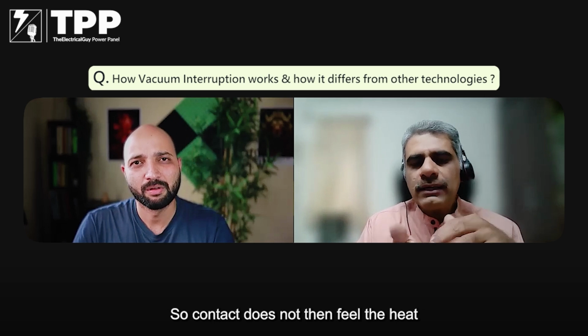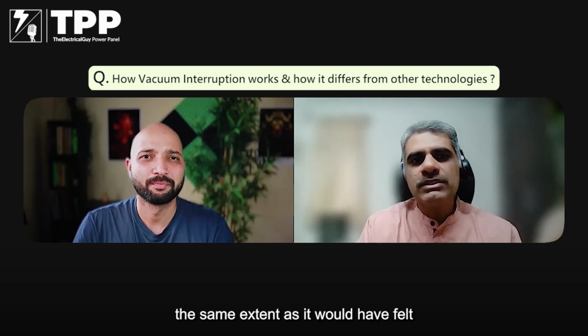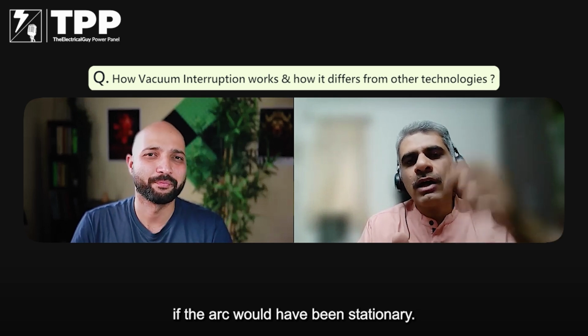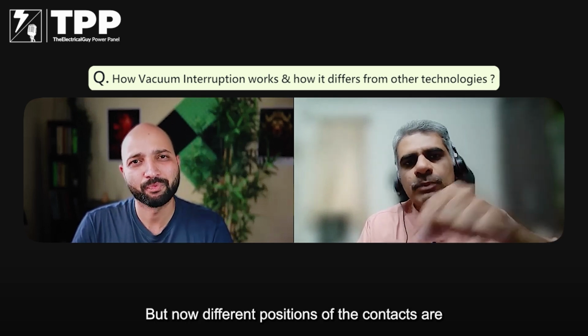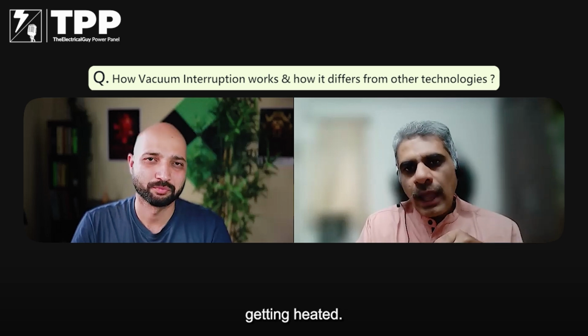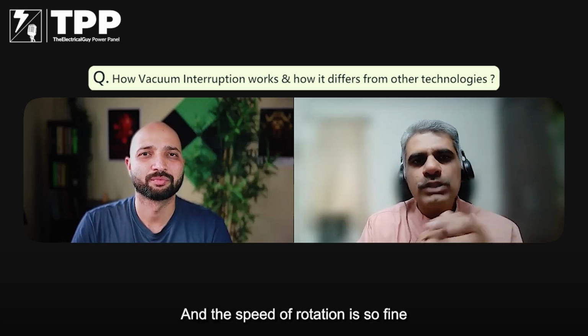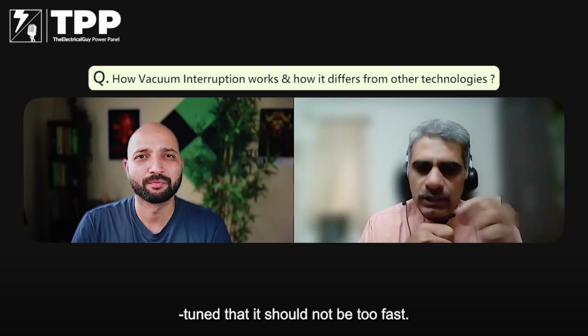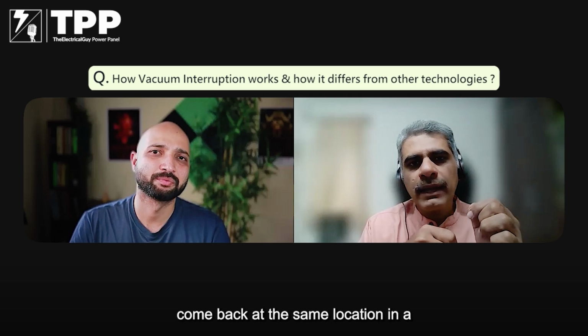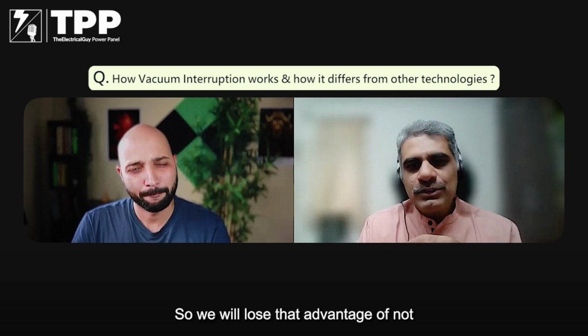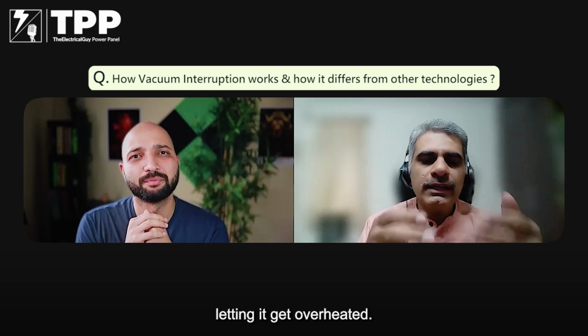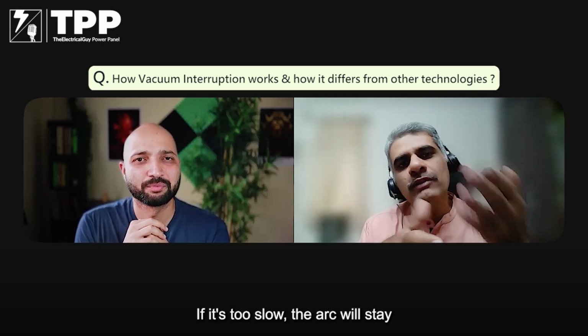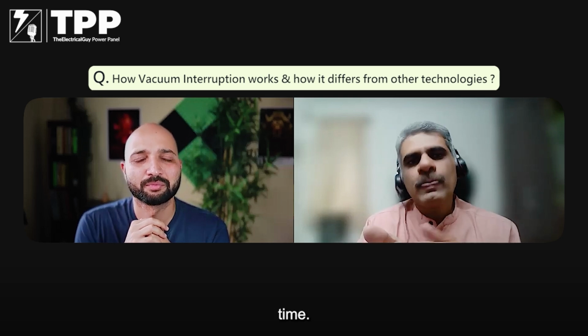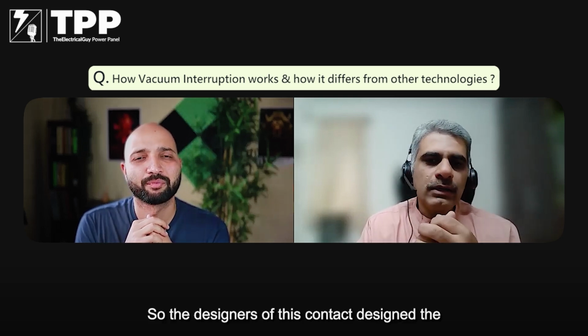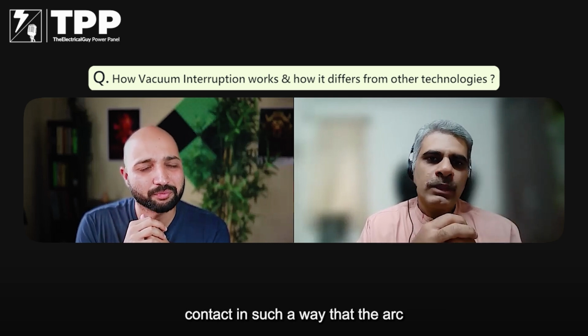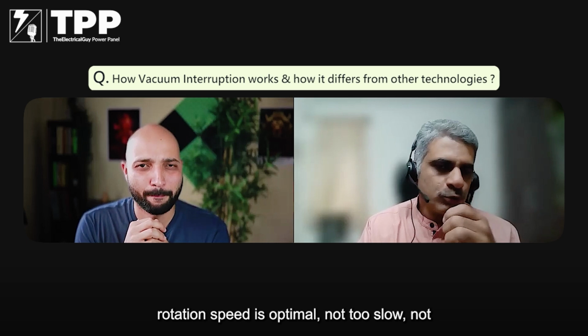So the contact does not feel the heat to the same extent as it would have felt if the arc had been stationary, because now different positions of the contacts are getting heated, and the speed of rotation is so fine tuned that it should not be too fast. If it's too fast, then the arc will come back at the same location in a very short time, so we will lose that advantage of not letting it get overheated. If it's too slow, the arc will stay at any particular location for a very long time. So the designers of this contact design the contact in such a way that the arc rotation speed is optimal, not too slow, not too fast.